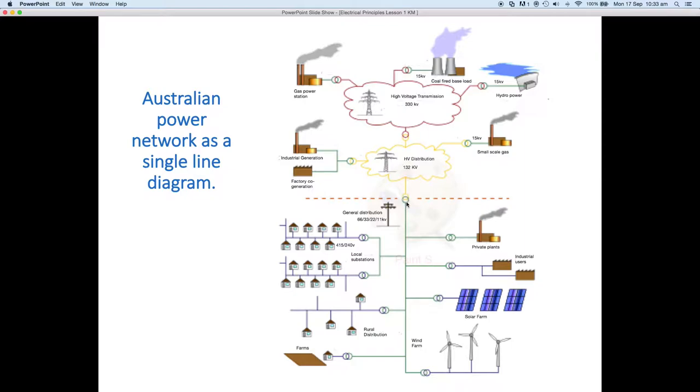As we get past distribution, we come down to this green section where we've got general distribution. General distribution can be at 66, 33, 22, or 11 kV, depending on which power supply or distribution company is where you are working. Then it drops down into substations and finally pole mount substations or pad mount substations, where the supply is dropped down to 415 and 240 volts for your local consumption.